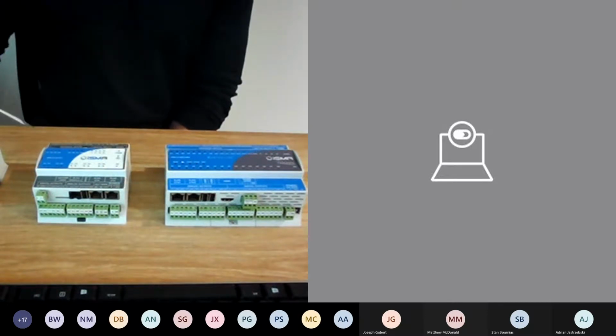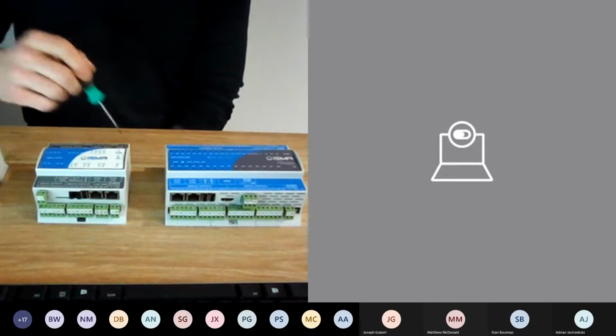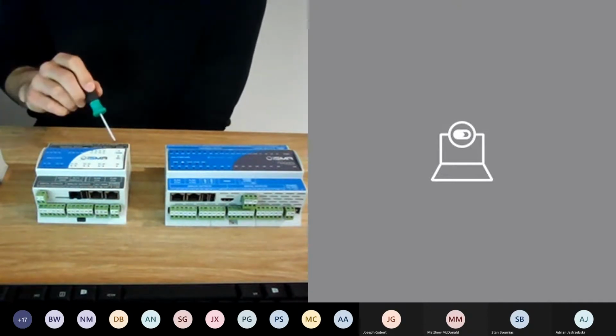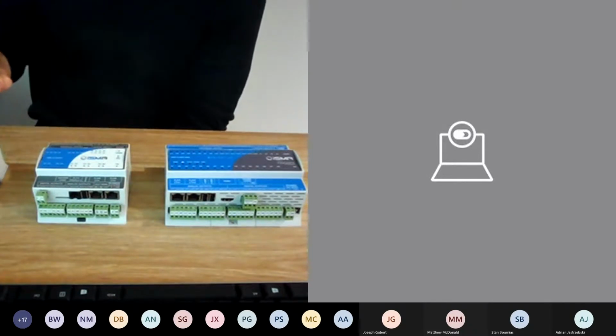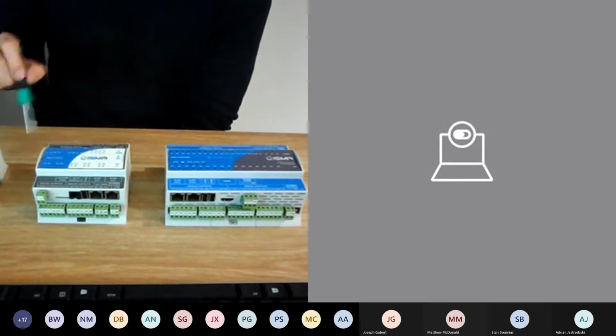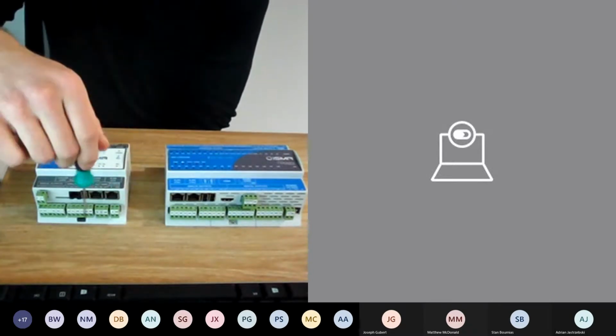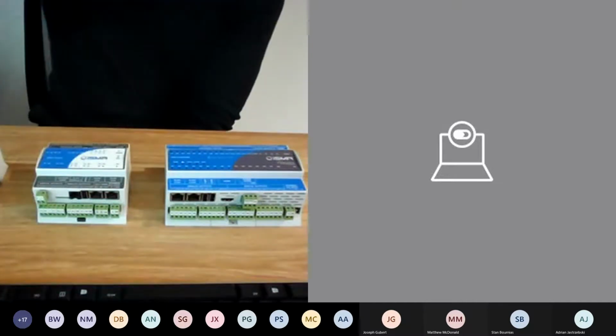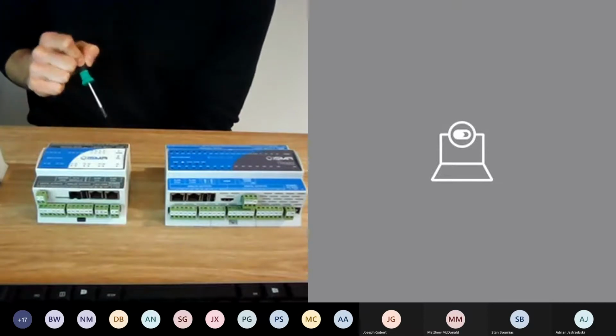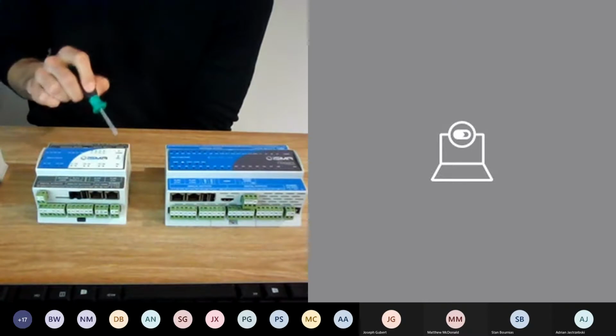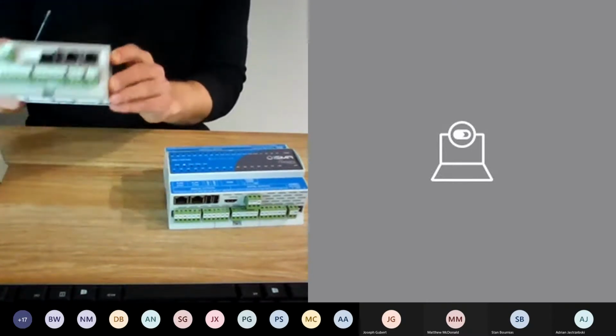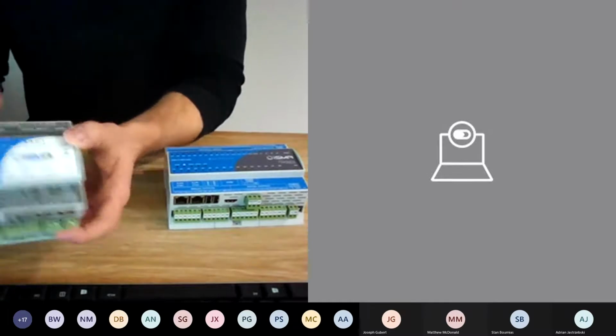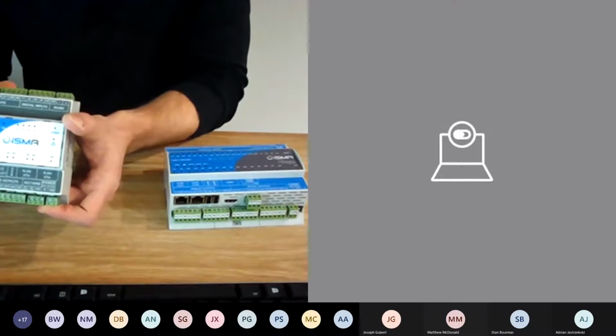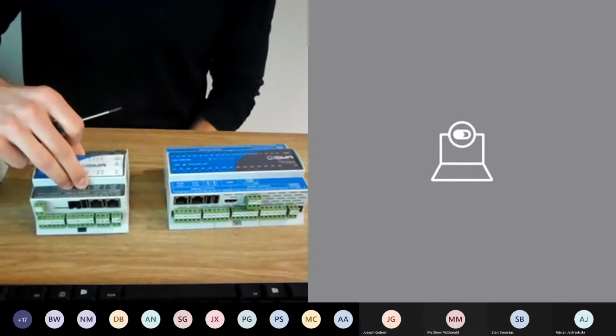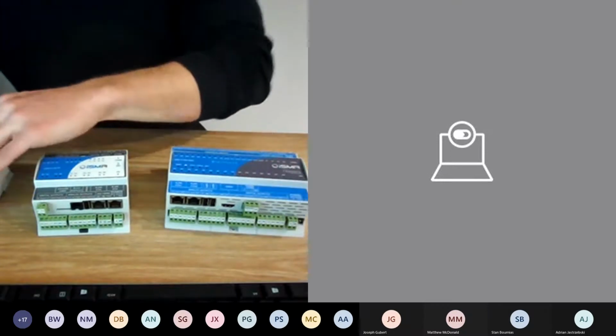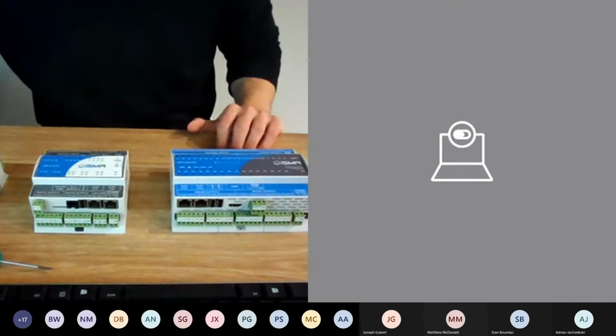Why? The reason we can do this is that Mix18 IP provides gateway functionality. So this RS485 of the Mix18 IP is giving us a Modbus TCP gateway. So we can connect to the Mix18 and we can connect multiple devices here to extend our network. You have to keep in mind, this is one catch, that this RS485 of the Mix18 or any other IP module that we have is master only, so it cannot act as a slave. It can only provide the functionality of the gateway. So you have to be aware of that. So this is the introduction about that.